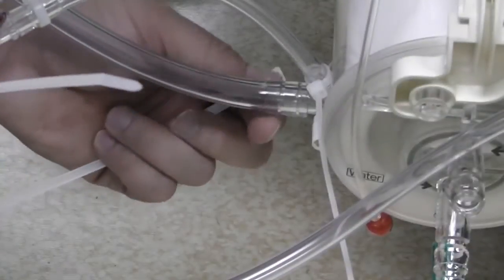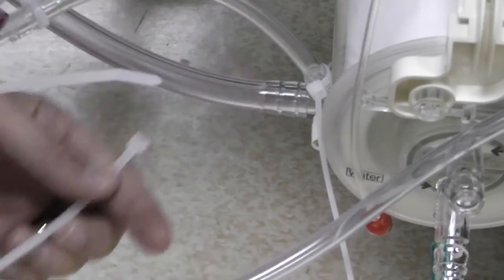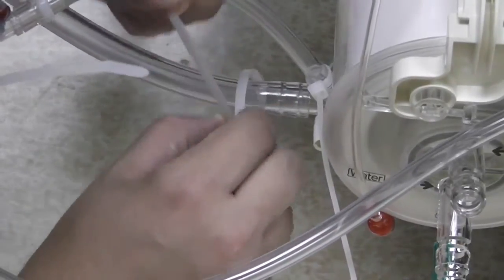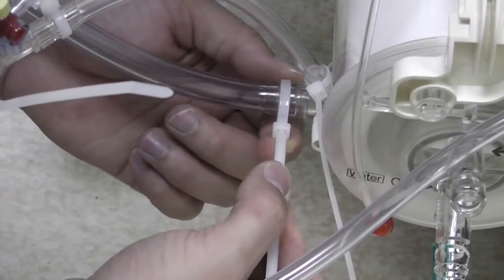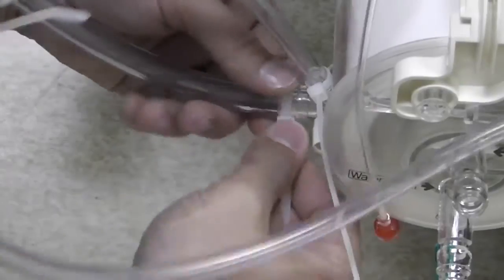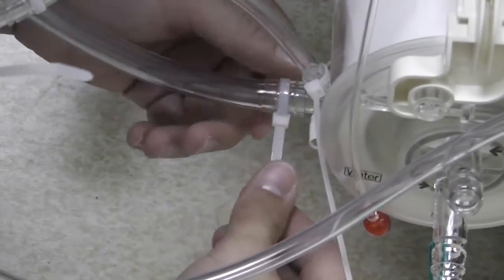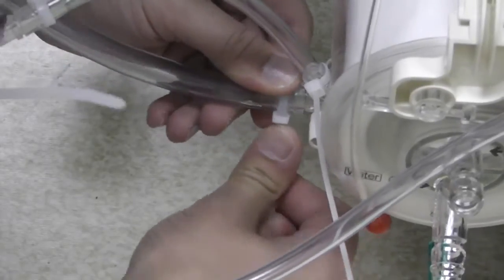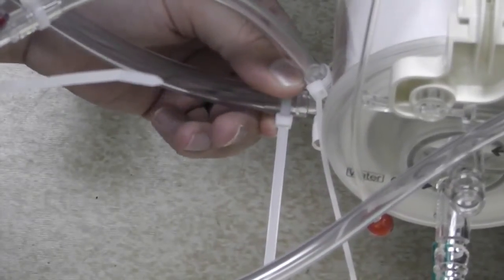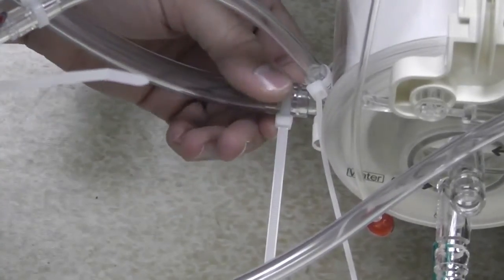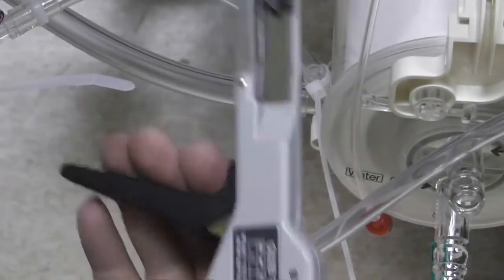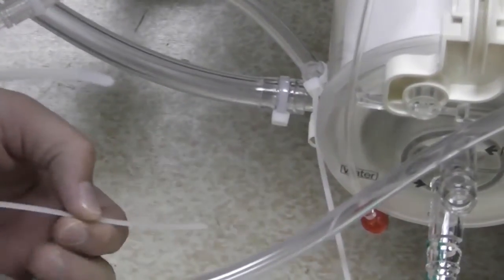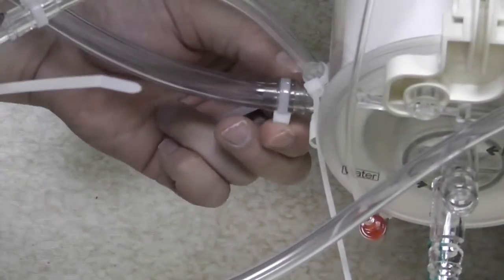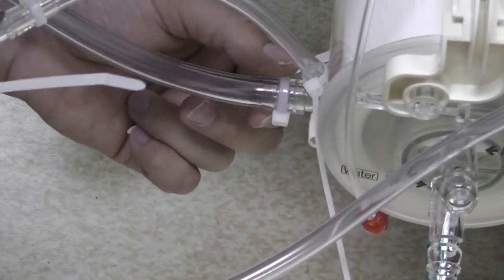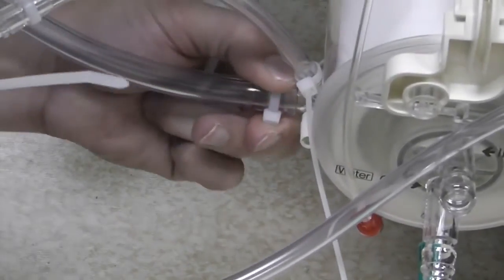Okay, so I'm at the outflow from the oxygenator with the arterial line here. So you just take the gun tie, wrap it around. I like to put these between the first and the second barb and snug it down and kind of crank on it a little bit. I mean, support the connection with your hand to make sure you don't break anything. But the whole point of these gun ties is to help prevent these lines from popping off. So you really want these to be snug. And then you just take your gun, put it on, squeeze the trigger, and it will tighten it another ratchet or two if it's able to, and cut it off. And afterwards, you should not be able to spin that. If you can rotate that, it's not tight enough.